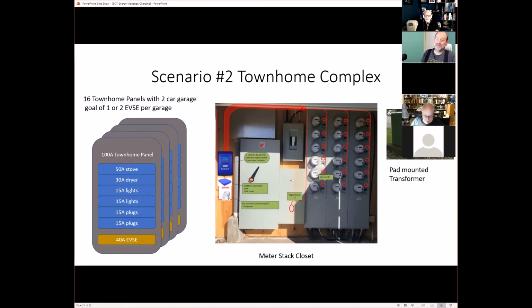So it was very convenient to add another 40 amp EVSE into that 100 amp panel, but you're likely overloading it, since you already have a 50 amp stove connection, a 30 amp dryer, lights and plugs, and sometimes air conditioners. So you're probably overloading that 100 amp panel just by installing a standard 40 amp EVSE.